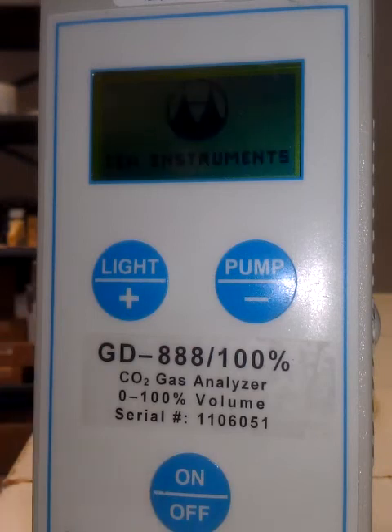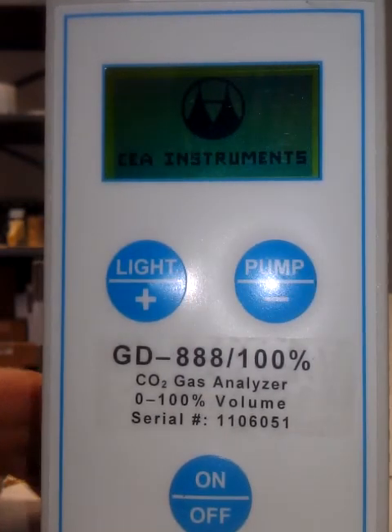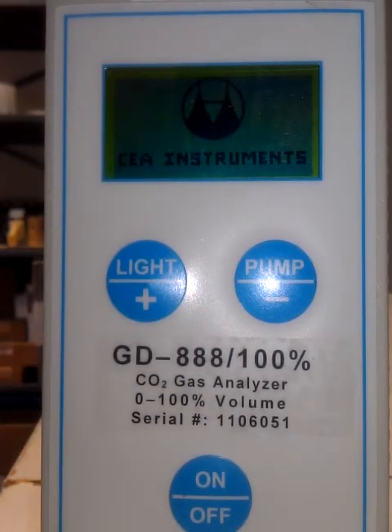And now, when you turn it on and it goes through all those tests, it is calibrated. You can check it again when it goes through by turning off the pump and introducing the gas and seeing that it does go there. Then you can confirm your unit is calibrated. Roughly clean air should be around 0.0%. Pump off, introducing 99.99 CO2. The unit reads 99.99 CO2. You have it calibrated. You do that with all three of the units in a fire suppression 3-point, and you now have a completely calibrated 3-point unit.